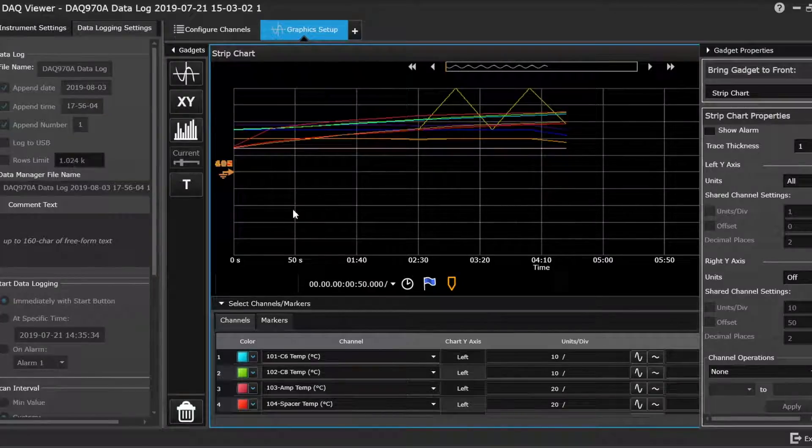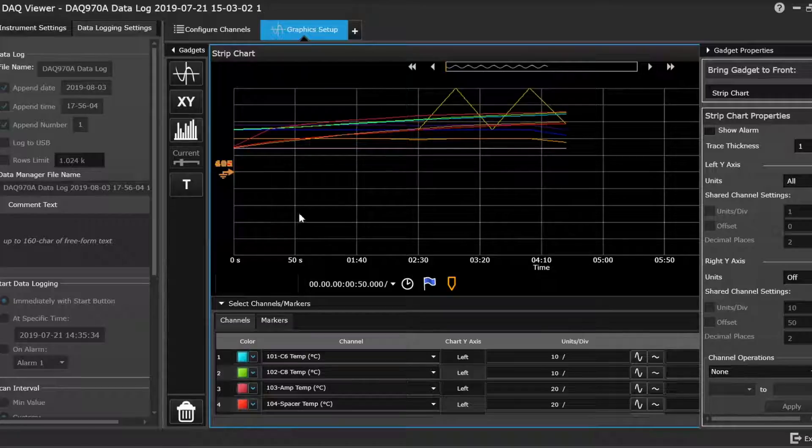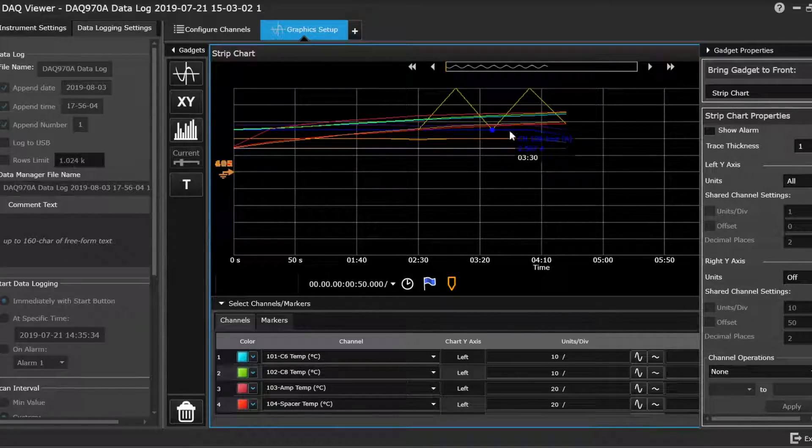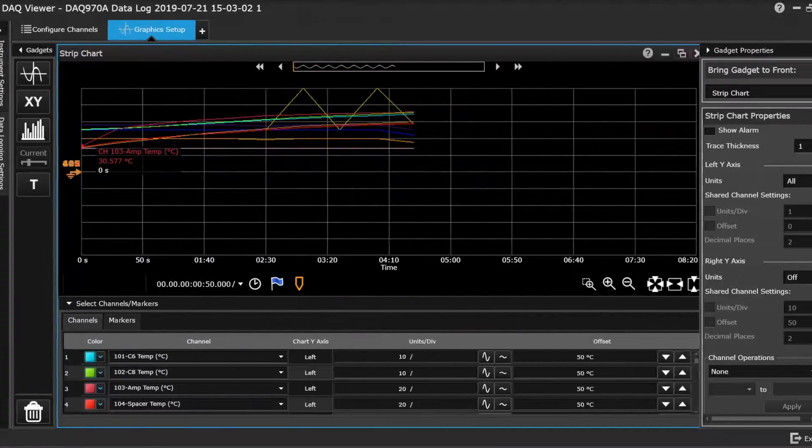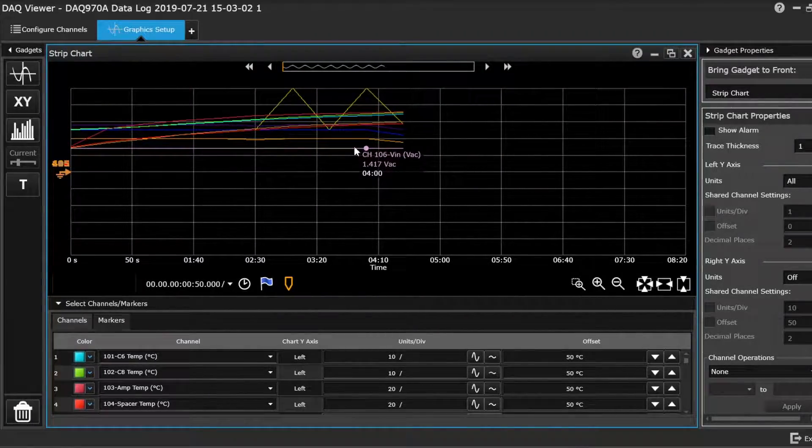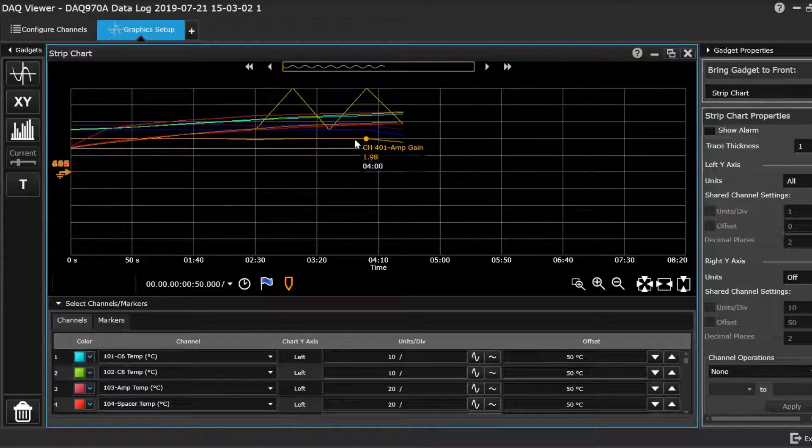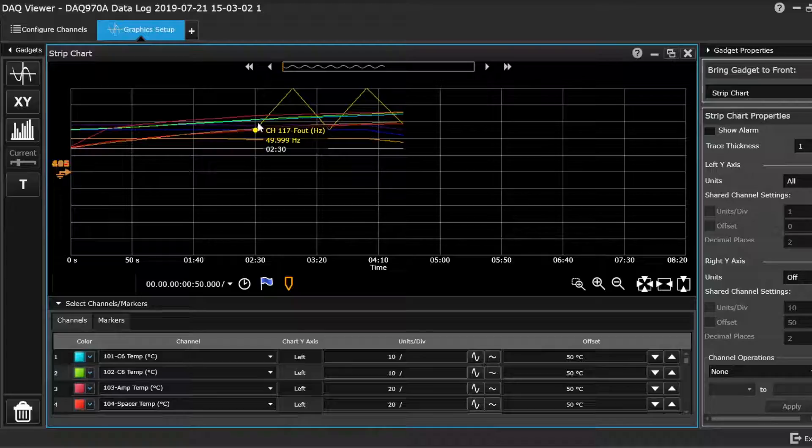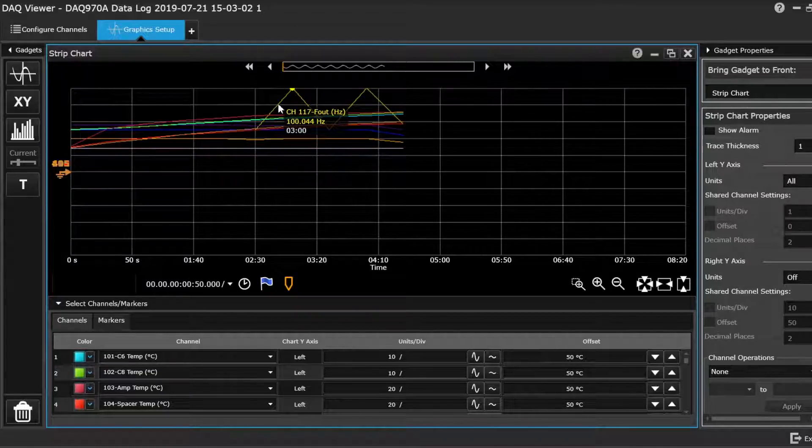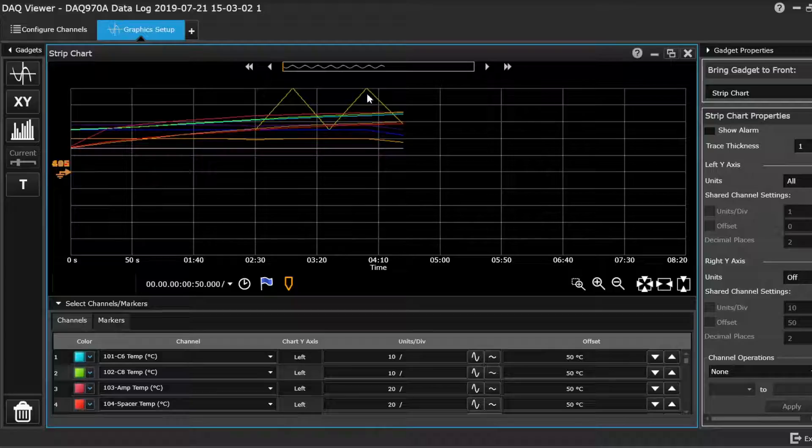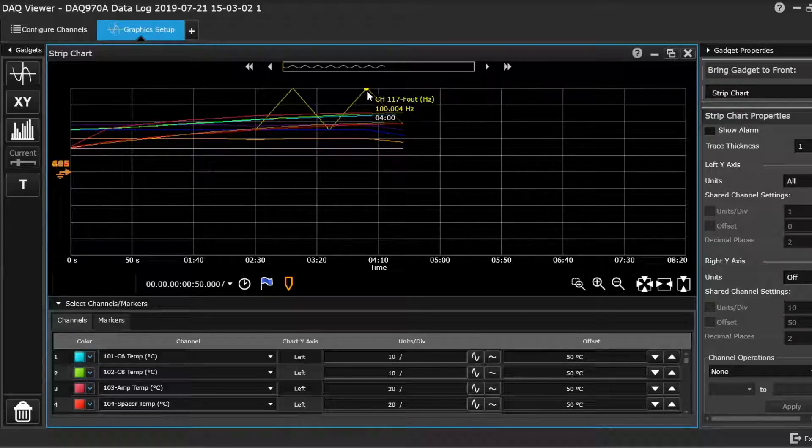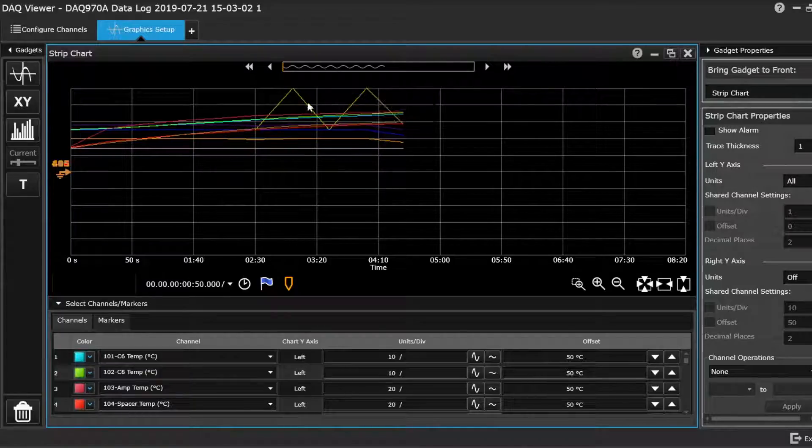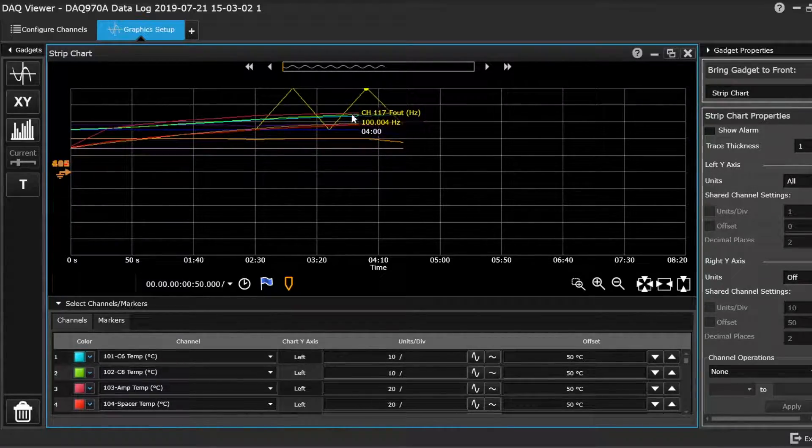So once the data collection has completed, you're left with your strip chart here. It shows you all the trend plots. I'll shrink it out of the way and get a fuller screen. You can actually hover over each channel and it'll identify it for you. And like you see up here, we've got a couple of excursions. Frequency out went up to 100 hertz on a couple of occasions, which is surprising. That's not something that I picked up when it was on the oscilloscope. So that's something there that I'll need to have a look at.